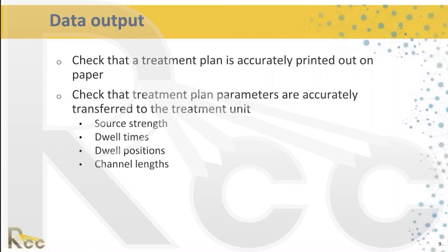Once applicator modeling is verified, we must confirm that the treatment plan is accurately printed on paper, matching what is in the planning system. After exporting data to the treatment console, we compare the printed plan or PDF against what is represented at the console, verifying that parameters like source strength, dwell times, dwell positions, and channel lengths all transfer accurately.